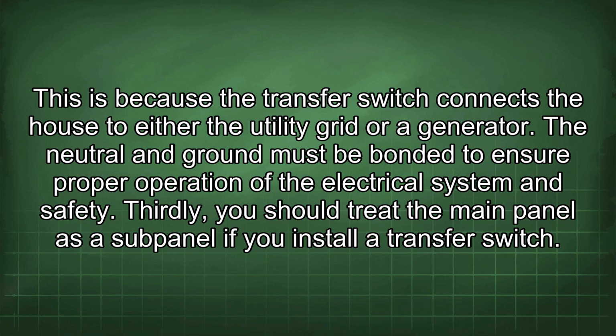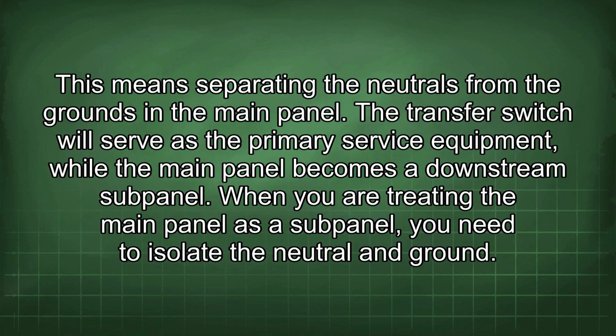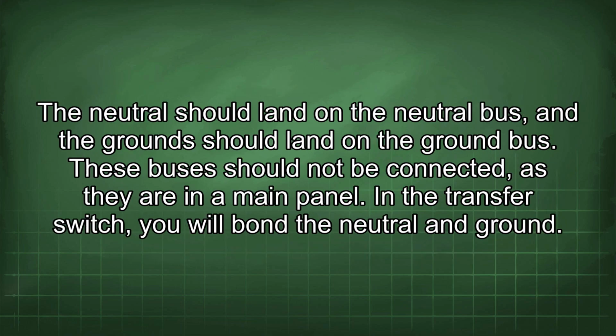Thirdly, you should treat the main panel as a subpanel if you install a transfer switch. This means separating the neutrals from the grounds in the main panel. The transfer switch will serve as the primary service equipment while the main panel becomes a downstream subpanel. When you are treating the main panel as a subpanel, you need to isolate the neutral and ground. The neutral should land on the neutral bus, and the ground should land on the ground bus.